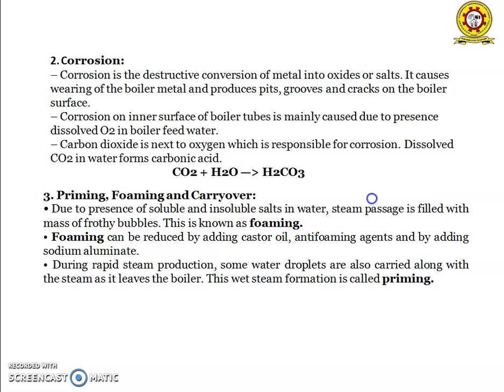The corrosion is caused by acid or low pH, in addition to dissolved oxygen. Oxygen present is mostly responsible for all the other factors. Oxygen generally enters a closed system through makeup, condenser leakages and pump packings. Carbon dioxide is next to oxygen in being responsible for corrosion.